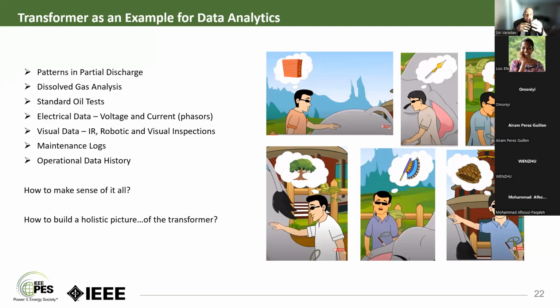So the idea here is, if I'm looking at a transformer - let's say my elephant is a transformer - I can get partial discharge patterns, dissolved gas analysis patterns, standard oil tests. These are all like single views of looking at one aspect. It's like blind man number 1, blind man number 2 - each of them is looking at one aspect of the transformer, in this case the elephant.